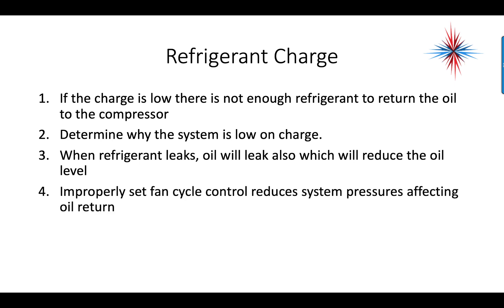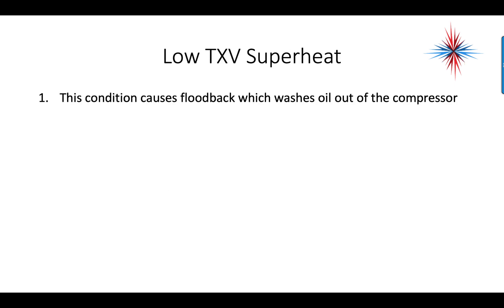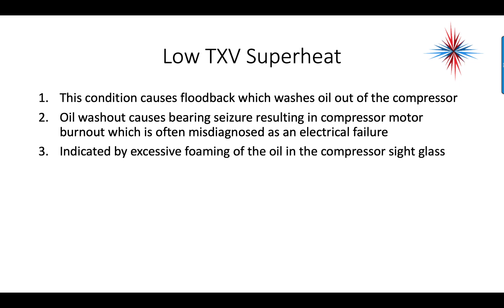Improperly set fan cycling controls reduce system pressures, affecting oil return. Low TXV superheat is another condition that causes oil issues — this condition causes flood back, which washes oil out of the compressor. Oil washout causes bearing seizure, resulting in compressor motor burnout, which is often misdiagnosed as an electrical failure. This is indicated by excessive foaming of the oil in the compressor sight glass.